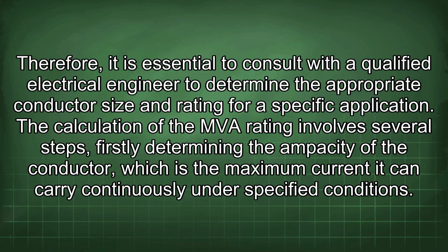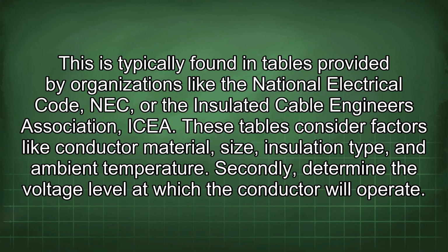Firstly, determining the ampacity of the conductor, which is the maximum current it can carry continuously under specified conditions. This is typically found in tables provided by organizations like the National Electrical Code (NEC) or the Insulated Cable Engineers Association (ICEA). These tables consider factors like conductor material, size, insulation type, and ambient temperature.